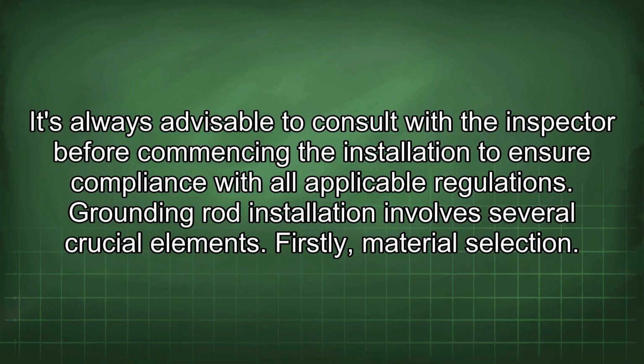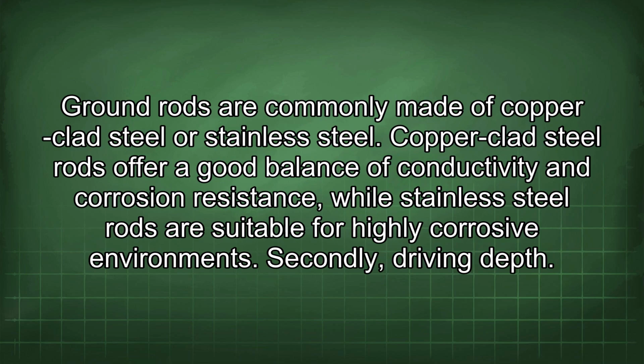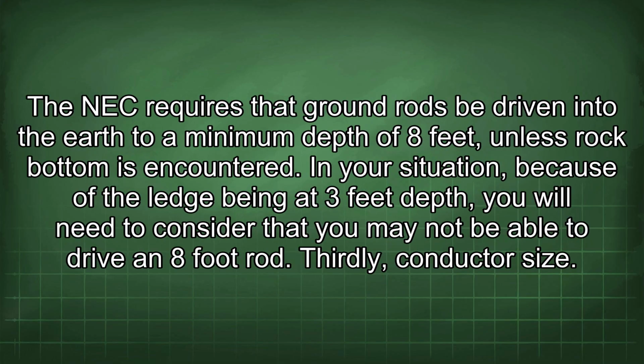Grounding rod installation involves several crucial elements. Firstly, material selection. Ground rods are commonly made of copper-clad steel or stainless steel. Copper-clad steel rods offer a good balance of conductivity and corrosion resistance, while stainless steel rods are suitable for highly corrosive environments. Secondly, driving depth. The NEC requires that ground rods be driven into the earth to a minimum depth of 8 feet unless rock bottom is encountered. In your situation, because of the ledge being at 3 feet depth, you will need to consider that you may not be able to drive an 8-foot rod.